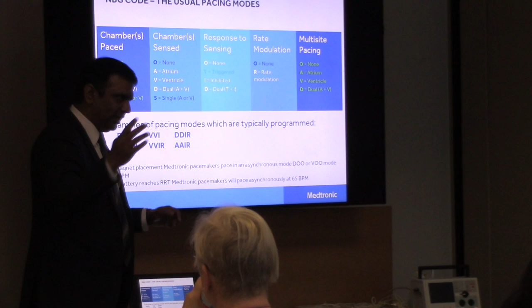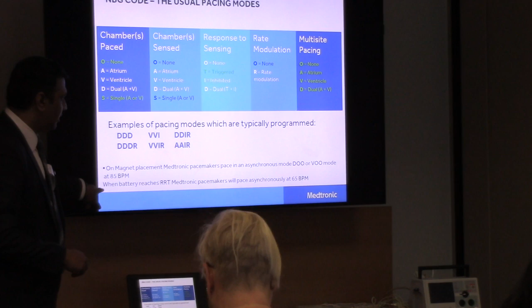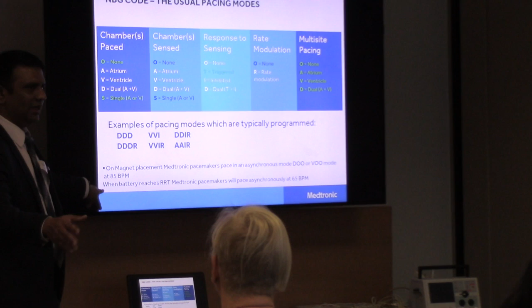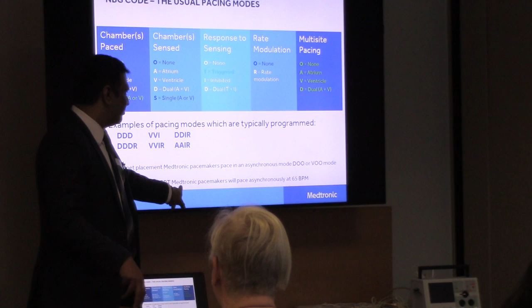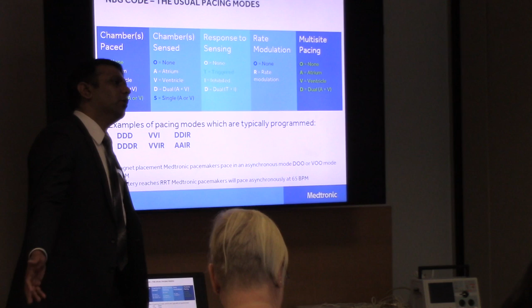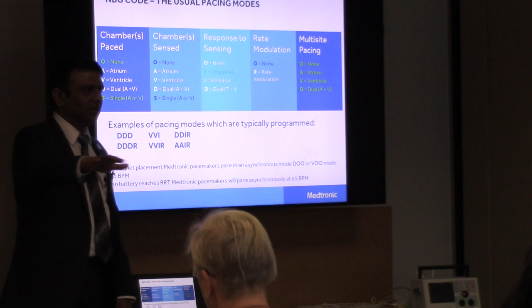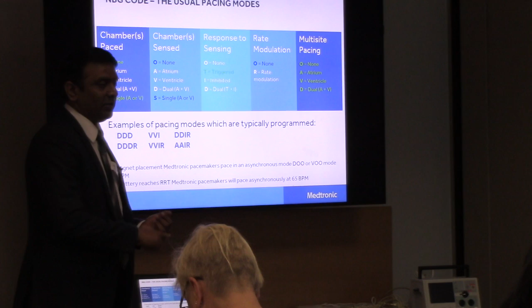It doesn't care about what the underlying rhythm is. And when the battery reaches RRT, or recommended replacement time, meaning that there are 3 more months left, Medtronic pacemakers on magnet placement will pace at 65. So if you want to evaluate a Medtronic patient's battery status, putting a magnet on would immediately tell you: look for spikes at 65. If you constantly see spikes at 65 after you place the magnet, their battery needs to be replaced. And if they're going at 85, the battery is fine. So a magnet can tell you a lot about the device, especially pacemakers. This is different for defibrillators.